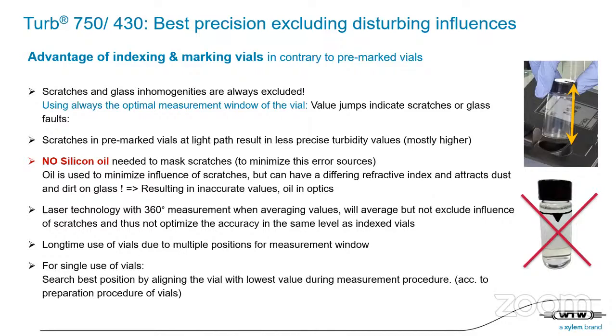And there is a big advantage in comparison to other procedures which are out in the market. First, we do not use the pre-marked vials. I explained it just the slide before. And we do not use silicone oil to mask the scratches, because we detect the scratches when marking and indexing, as it is described in the standard regulation, and we put no oil on a vial in an optical system. Oil in an optical system, particularly on the vial, is just attracting dirt and dust or fingerprints or whatever. So this always can impact the measurement result. Therefore, we go for the fast and quick measurement solution with the indexed vials, no oil.